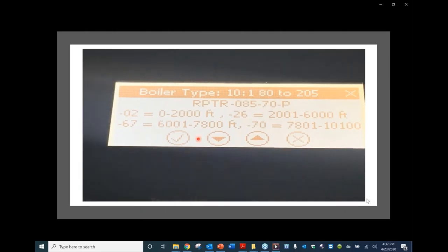Here it shows a Raptor, same boiler, it's an 85,000 BTU boiler, it's at 7,800 to 10,000 feet, and this one's propane. Making the fuel designation changes the fan speed, sometimes changes the light off rates, changes max fan speed. All that information can be found in the I&O manual in the charts.